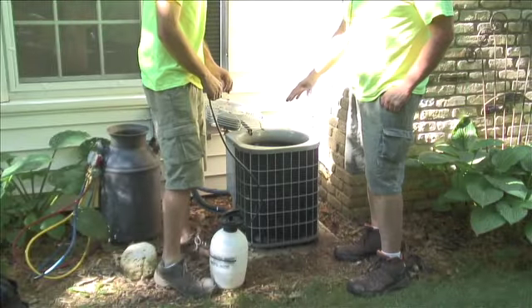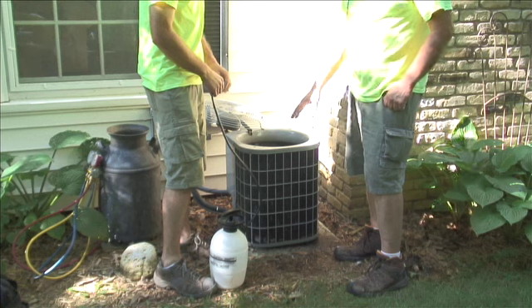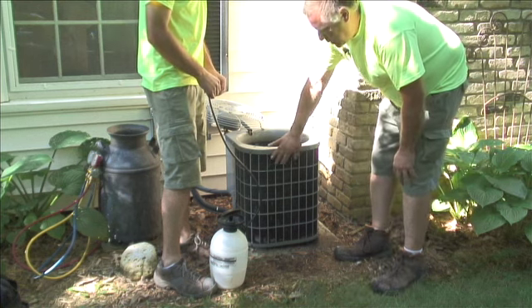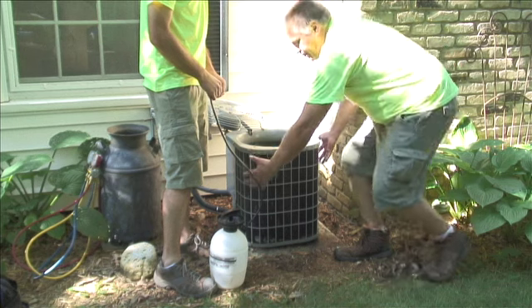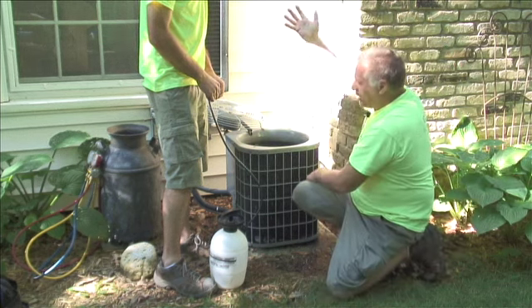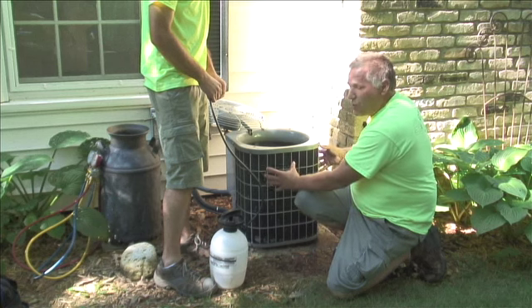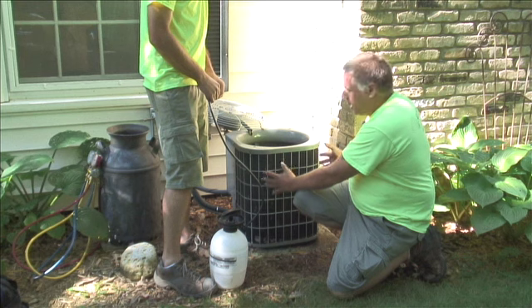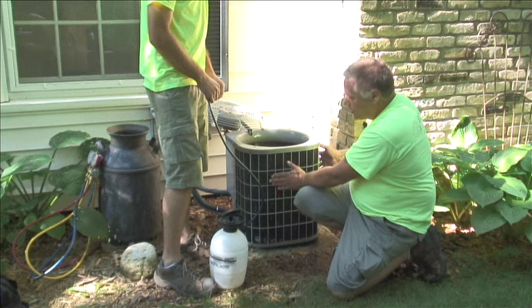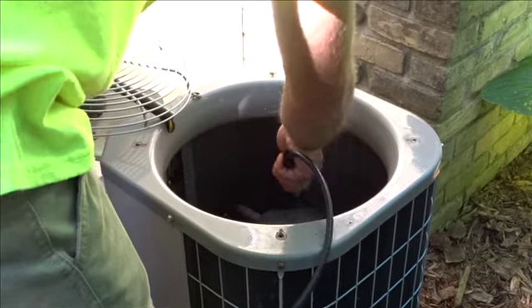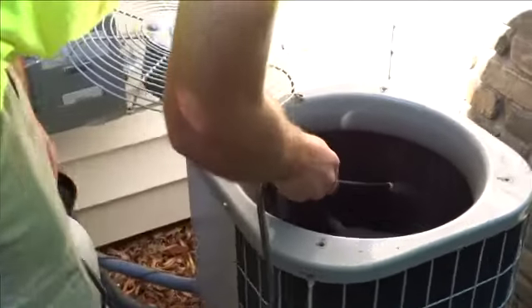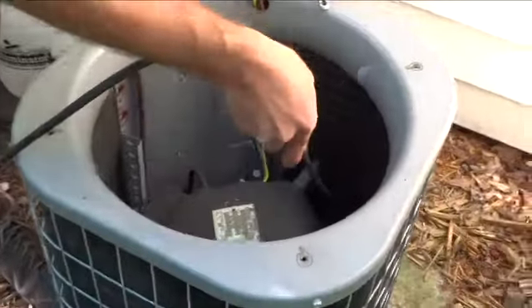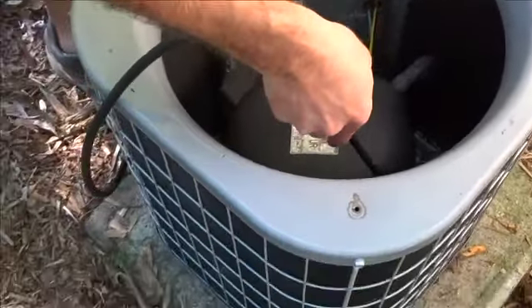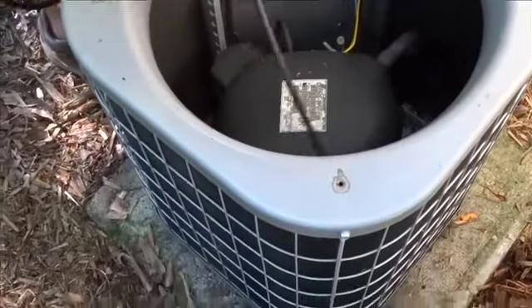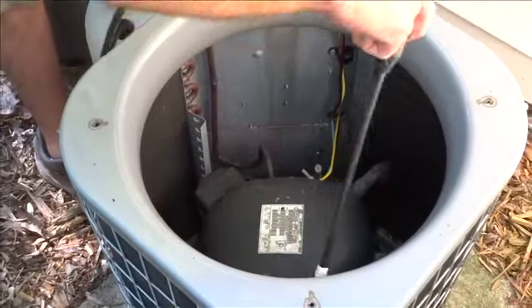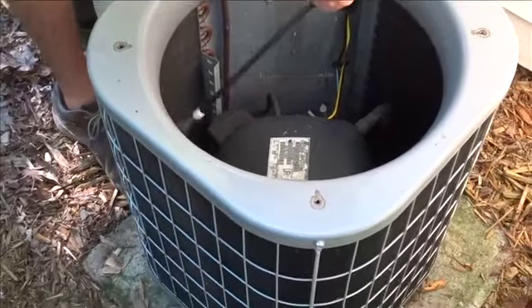Now we'll be spraying. This is an acid cleaner. We spray on the outside. The air conditioner draws from the outside and discharges up the top, so when it's drawing in the outside air, it's pulling in all the dust and dirt. In here it gets trapped in these fine fins on the coils. This acid gets in here and foams and eats out all the dirt in between the fins. It's very tight, so the cleaner the fins are, the faster the air conditioner can dissipate the heat, and the less it'll run and the cheaper it will be on your electric bill.